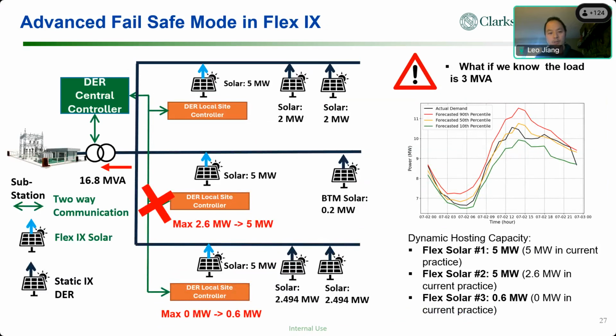Now this is the fail-safe mode. For example, if the smart inverter local controller loses communication with the central controller, as in the figure, currently the controller will use the static allocated hosting capacity for the curtailment. That's to protect the grid asset and make sure that when there is no communication, your smart inverter output is limited by the static hosting capacity. For example, in the figure, for the second solar farm in the middle, the static hosting capacity allocated to this site, when there is a loss of communication, lets the smart inverter output a maximum of 2.6 megawatts. For the third solar farm at the bottom, the allocated static hosting capacity is 0.